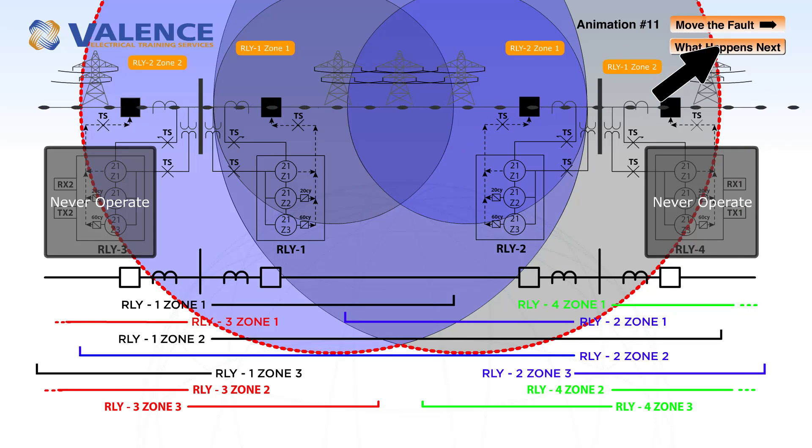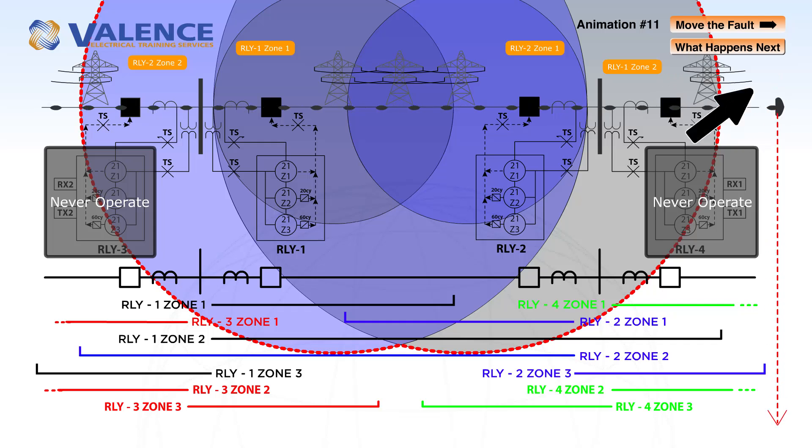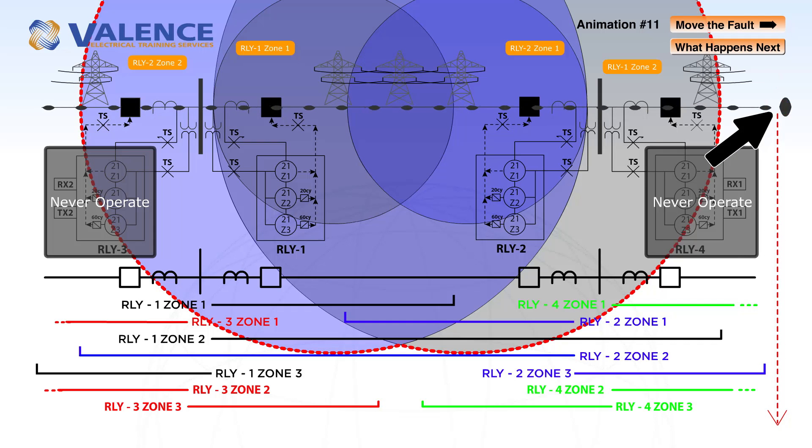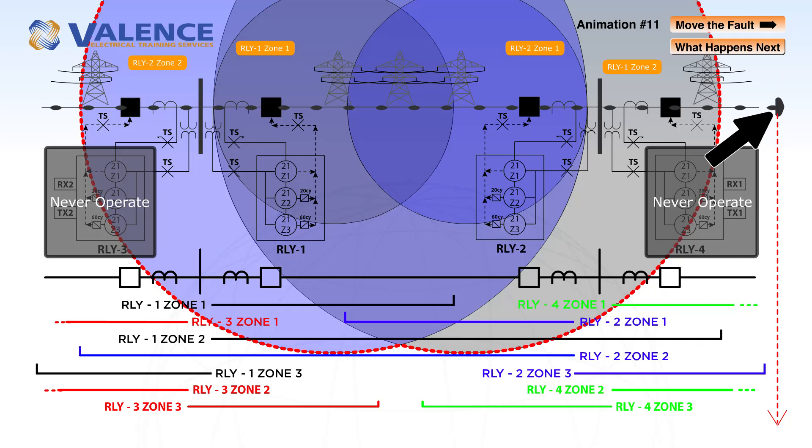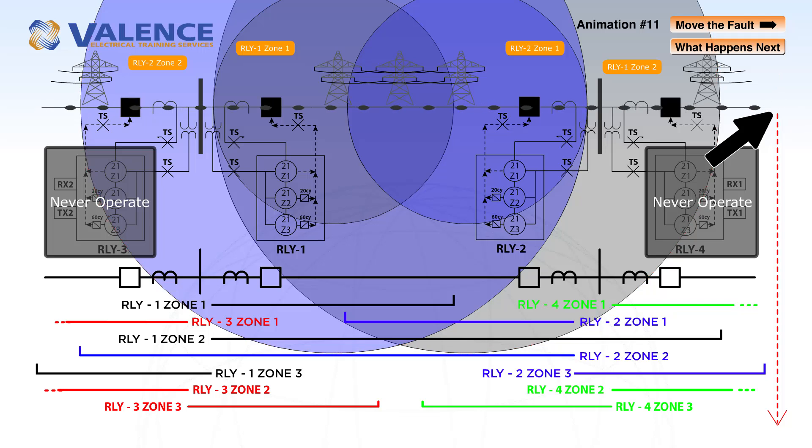If we move the fault completely outside of both zones, nothing will happen because it's outside of the zones of protection for both relays.